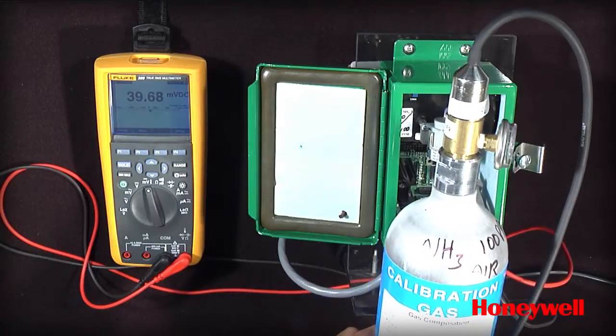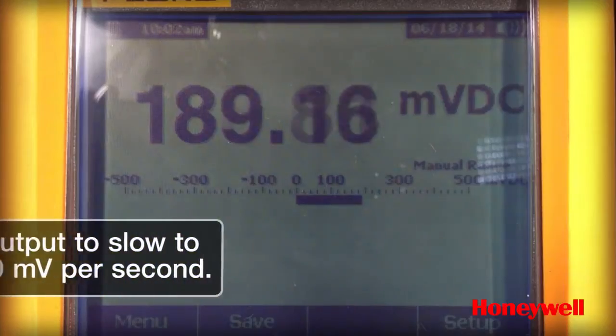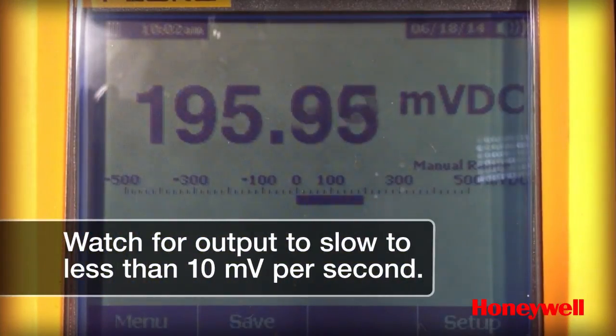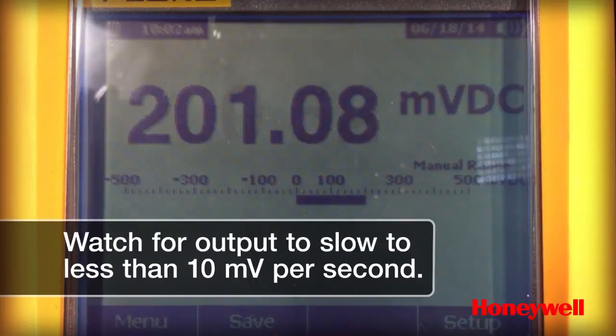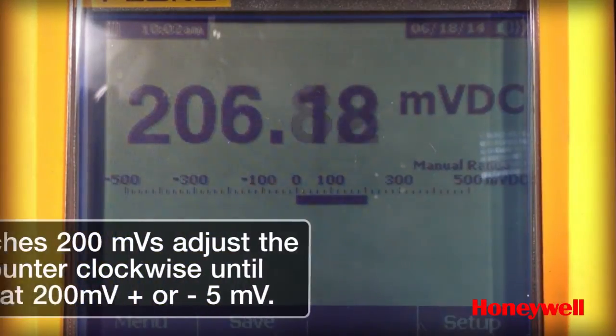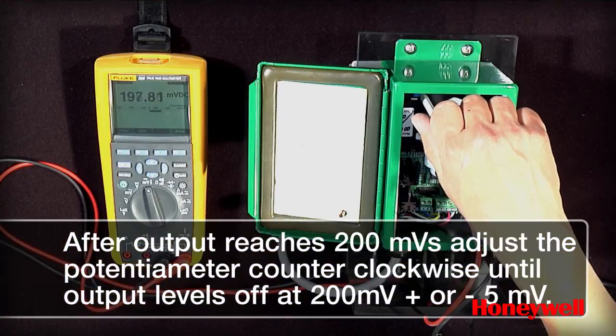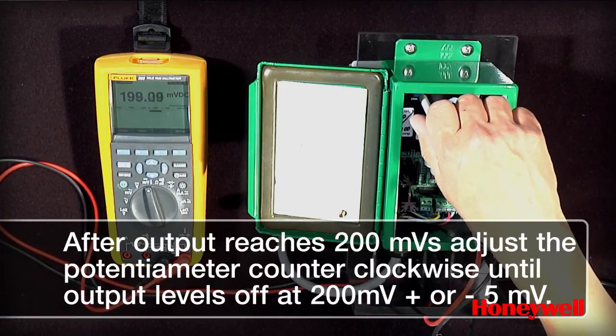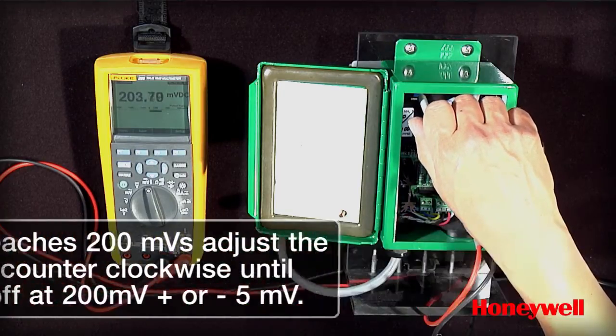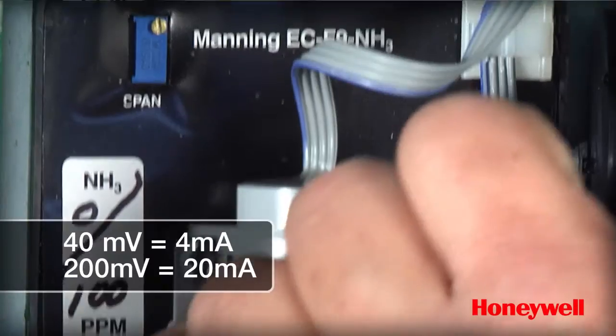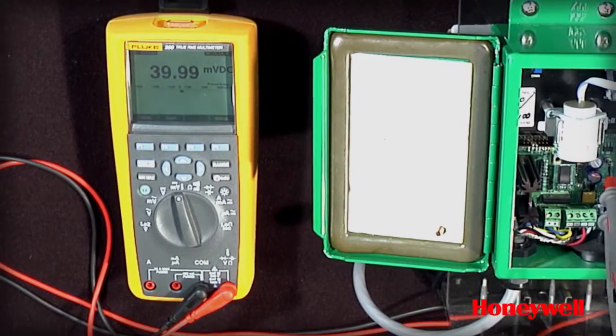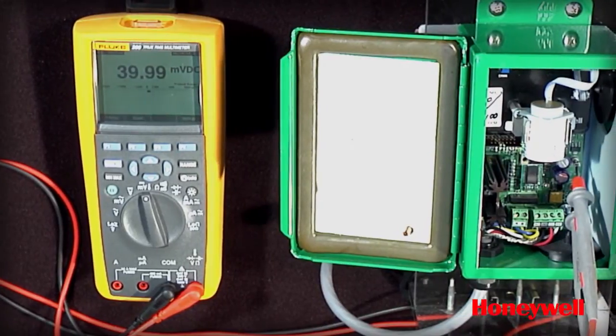As the gas flows, watch the output on the meter until it slows to rising less than 10 millivolts per second. When it reaches 200 millivolts, you will start to adjust the potentiometer counterclockwise to get it as close to 200 millivolts plus or minus 5 millivolts. When that output is achieved, turn off the gas flow, pull the adapter off the cell, and the Honeywell EC-FX is now calibrated and ready for operation.